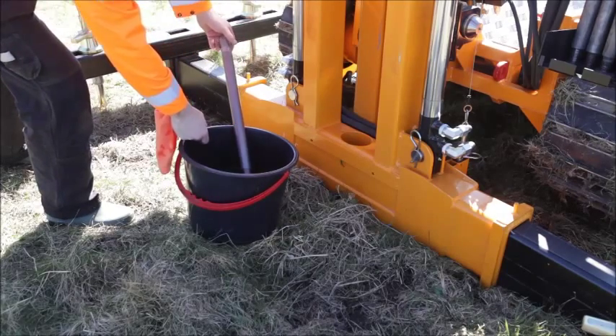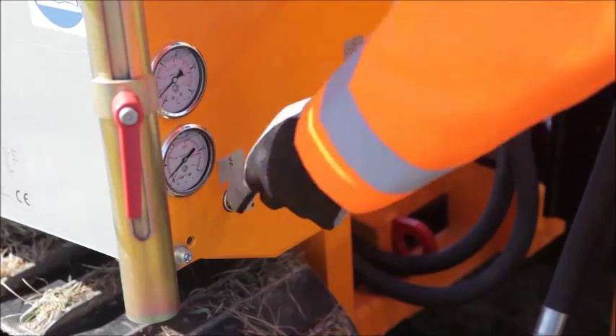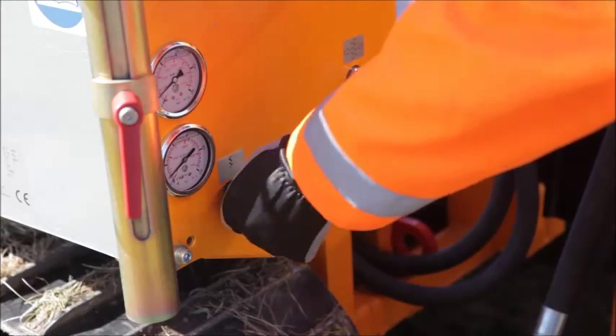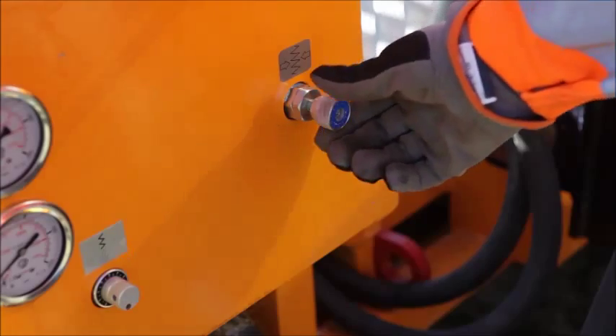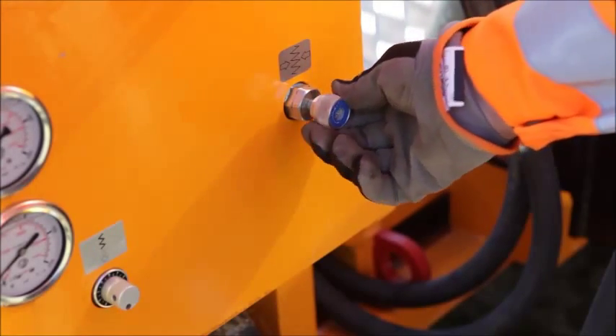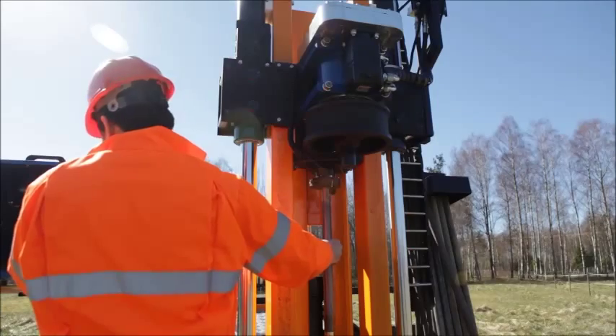For standard CPT testing, the speed should be set to 2 cm per second. Protect the equipment by adjusting the pushing force in regard to the ground conditions.